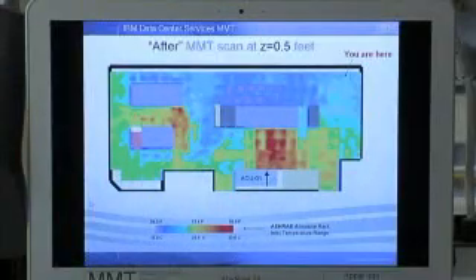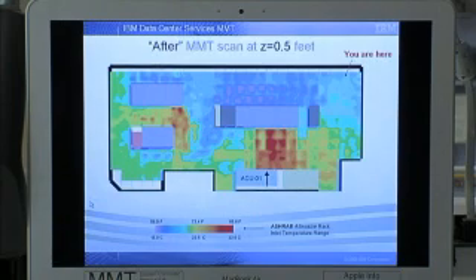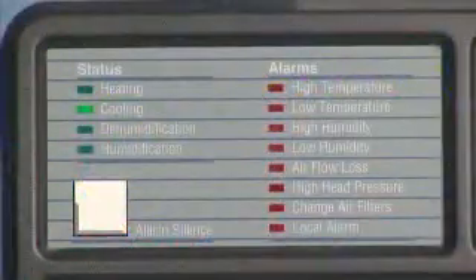Once we update the data center with the proper hardware, placement of the perf tiles, placement of the water-cooled hardware, we then go back in and verify everything, make sure it meets all our specifications. So we go back in and rerun the MMT tool, the mobile measurement tool, take data throughout the data center, create the 3D profile of that, check all our temperatures, look at the ventilation, and make sure we're all in specs. And based on that study, everything was in spec, we were optimized, we were fully utilized on the computer room air conditioning unit, and we didn't have any alarms that were going off.